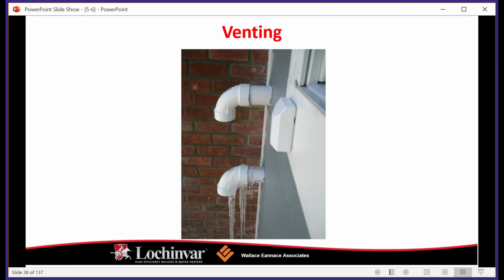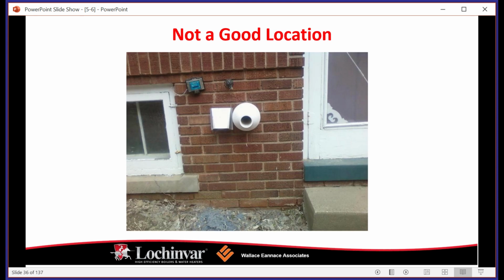Again, venting, one of the things, actually on this slide, we can go back to this one. Good to remember as well, and again, you can go more in depth with this, all the venting material, all the venting lengths, all the venting best practices are going to be laid out for you in the manuals that come with your equipment. So during the winter months when these boilers and water heaters are running, the flue gases are going to contain some water, okay? So it's not uncommon to see water dripping out of a condensing boiler's flue pipe.